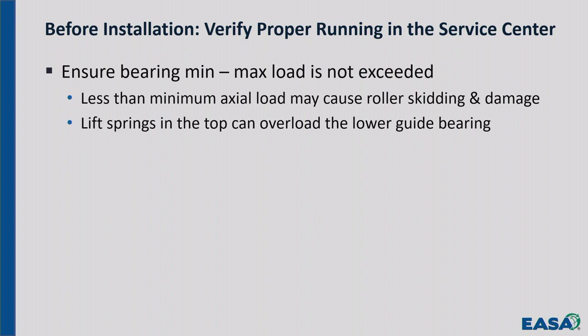And you can calculate the spring tension. Now, you can measure the spring tension pretty easily. Just set it on a scale and push down and compress it to the height that it'll be compressed when it's installed, and see how many pounds of force it is, multiply by the number of springs, and you know how much force you've got. Then you can look at the maximum axial load on that guide bearing and be sure that you're not exceeding it. Okay? So that's a concern.